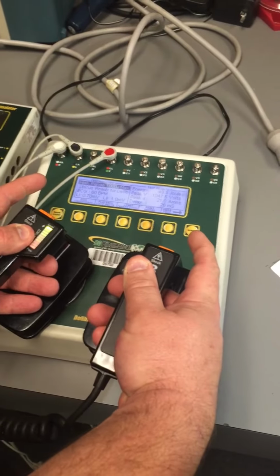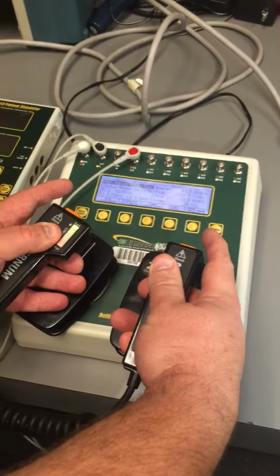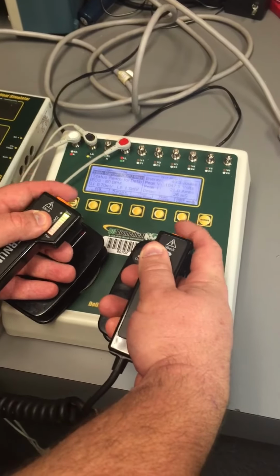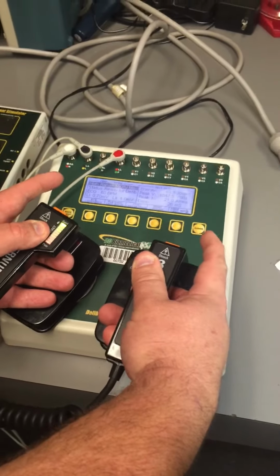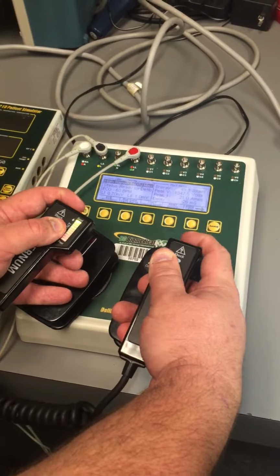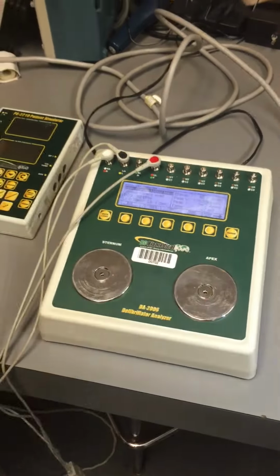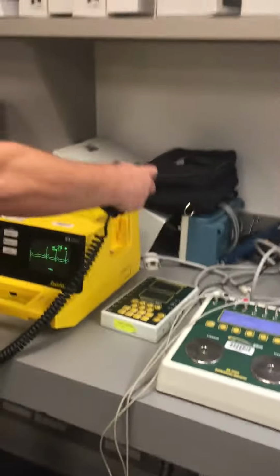Here, check this out. I was holding both buttons there, but I let go before it hit the peak of the R wave. I did it again. This time I'm going to press and hold. Okay. So it does not discharge until the peak of the R wave. And in this case, it was 27 milliseconds after the peak of the R wave, which there again is right in the middle of what we were looking for.